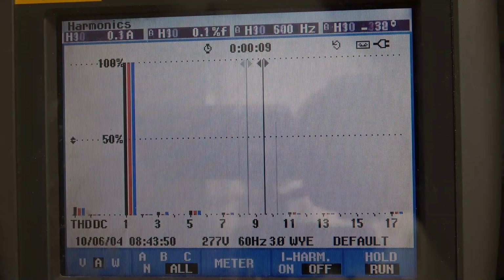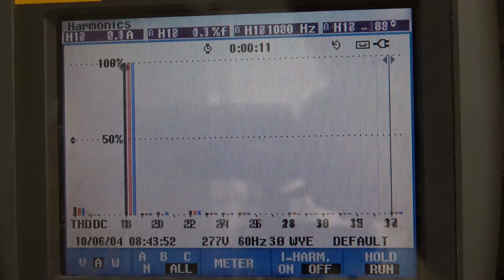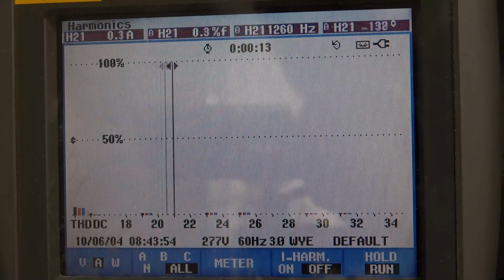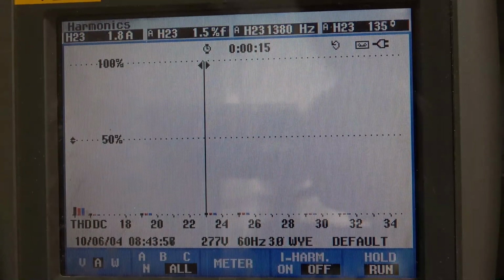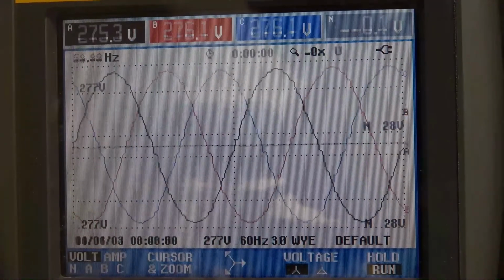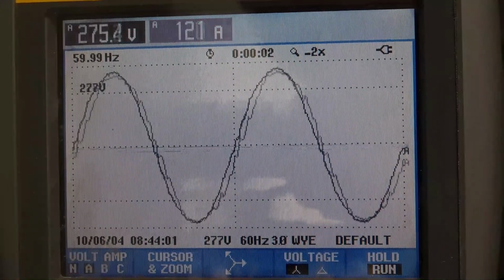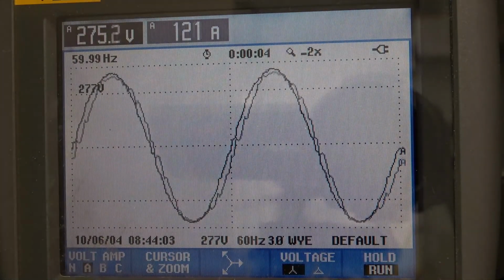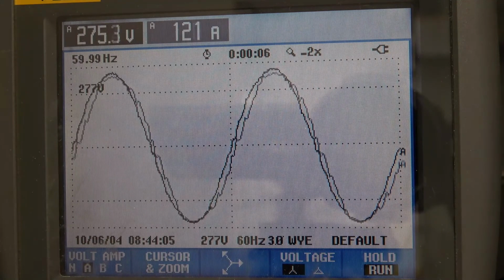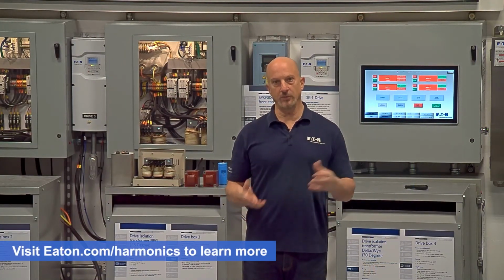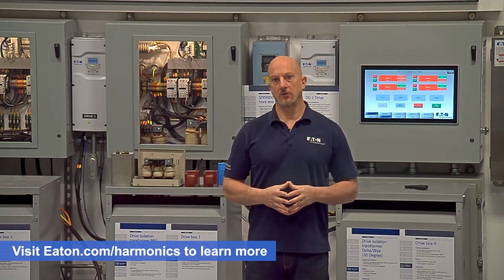So we have very, very minimal harmonics all the way out through, and we have a little bit of 23rd and 25th. But again, looking at the waveform, it's almost purely sinusoidal, and it's also very much in phase, which gives us that power factor correction that variable frequency drives offer as well. So even at a light load, we have a very good control of those harmonic currents.